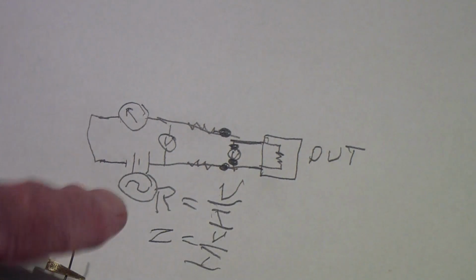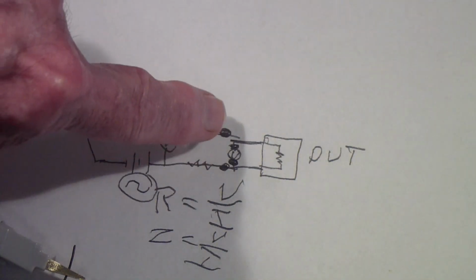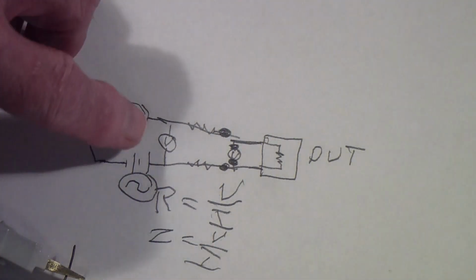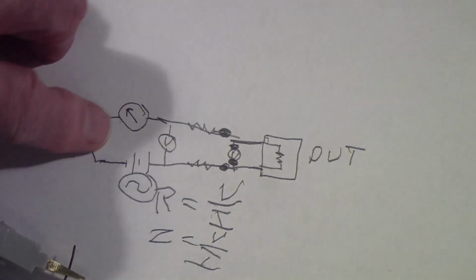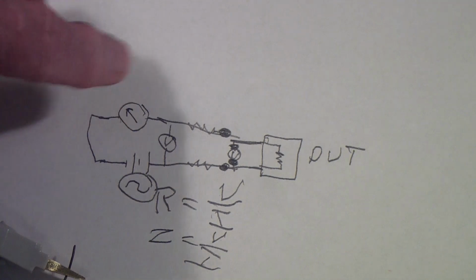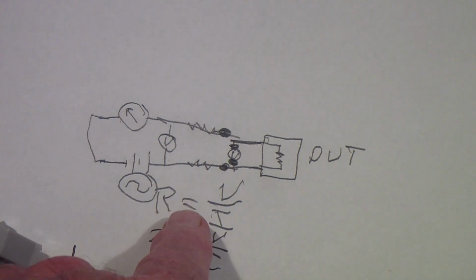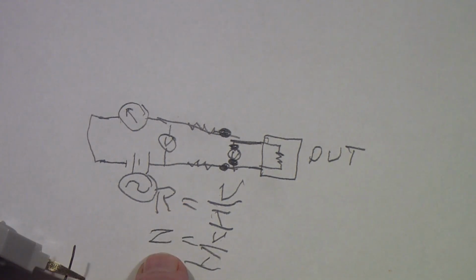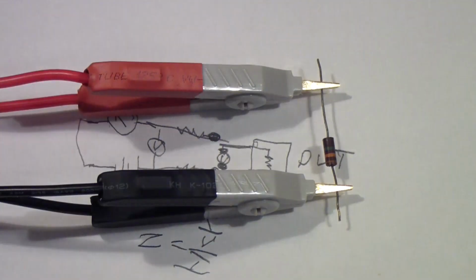So what happens is the current flows through the whole circuit. The voltmeter only measures the voltage across the device under test, not the voltage coming out of the test equipment. And from that you can compute resistance or impedance. By using 4 wires, you get an accurate computation of resistance or impedance.